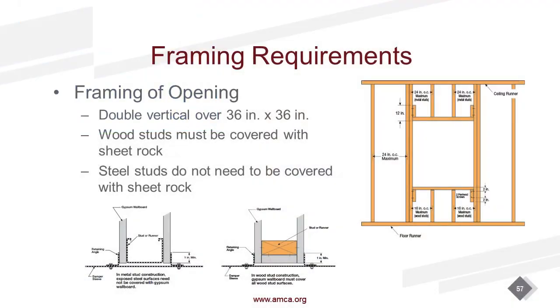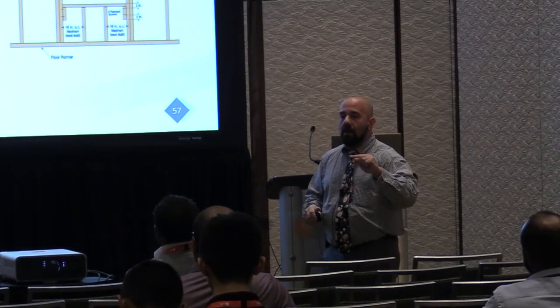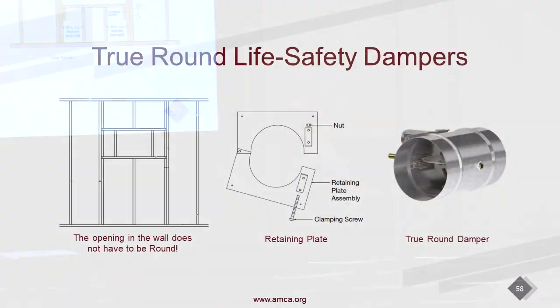So remember that. One thing we always like to point out in wood stud construction, wood stud walls, those openings need to be lined in sheetrock. Remember that. Steel stud, no. Wood studs, yes. That often gets overlooked, and that's a costly mistake. So we showed you those pictures of the different types of fire dampers, fire smoke dampers. Talked about square dampers. Now there's a true round damper. This is not a new technology. They've been around for quite a long time. Not every manufacturer actually has a true round damper, but there are advantages.